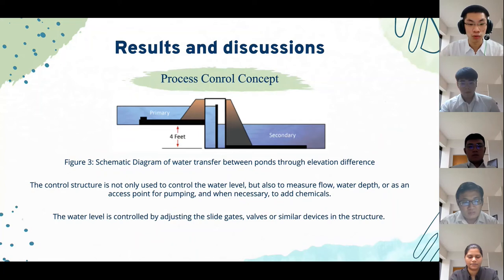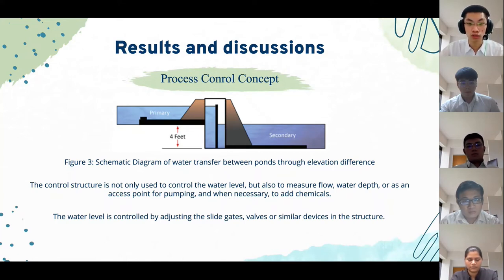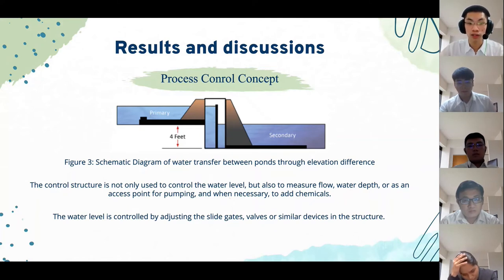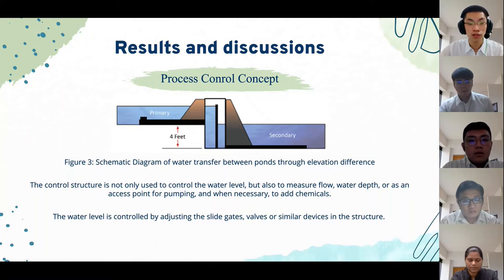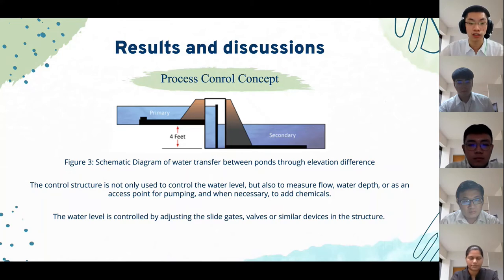Moving to the process control part, water transfer between ponds through the elevation difference method, as shown in this slide, will be applied. The control structure is not only used to control the water level, but also to measure flow, water depth, or to serve as an access point for pumping and, when necessary, to add chemicals. The water level is controlled by adjusting slide gates, valves, or similar devices in the structure.